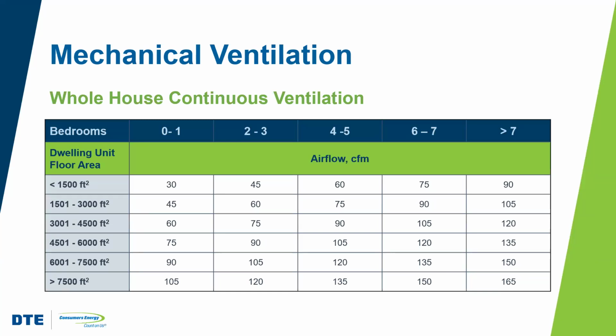Instead of local exhaust, we can also ventilate the entire house. Now, there are four approaches to this. We can use exhaust only, which, like local exhaust, removes air, but instead of just removing it from the kitchen or the bathroom, it removes it from the entire house. We can do supply only, which brings outdoor air into the home, and that can either be connected through the central air system, or it could have independent ducts, right? It could have its own ducts.